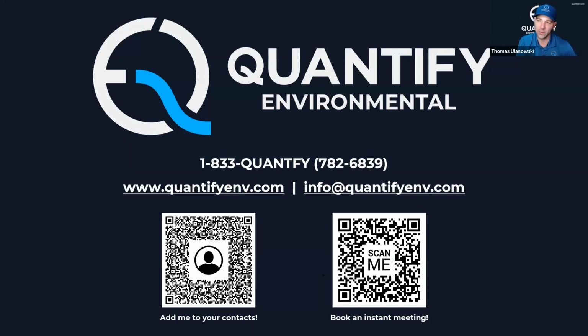That thermalator example Dave talked about in the Q&A slide was a perfect example of a piece of equipment someone already had, already running and configured for process temperature, but it had a 4 to 20 milliamp output. We can tap into that with our 4 to 20 milliamp receiver. We just do a single or 2-point calibration on the low and high end, translate that milliamps to temperature, and display it.